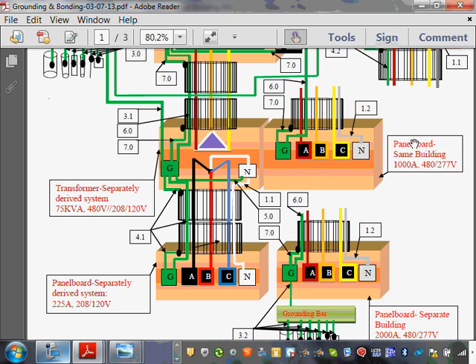Can you guys see that ultimately the neutral of the 277 and the neutral of the 120 are tied together at the source, right? If you follow this, they're all tied together where? At the source. They want you to tie them only at the source. That's all. So here's my newly created neutral. I bond it to the ground. That wire here, which could also be other than a wire, is called 5.0, right? That's my 5.0. That's called the system bonding jumper. Exactly like the name says, bonding jumper, except the term they use for it is system bonding jumper.